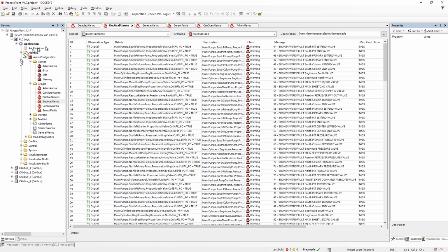Codesys provides a built-in alarm manager that has very good integration into the Codesys visualization. The Codesys Alarm Manager is designed to work best with traditional task-based procedural PLC programming, where the alarms are specified in a series of lists after the control design is complete. Unfortunately, creating and maintaining this list is tedious and error-prone, and the resulting complexity limits the use of the Alarm Manager to smaller PLC designs. The tool is definitely not well suited for today's larger and more complex PLC designs.